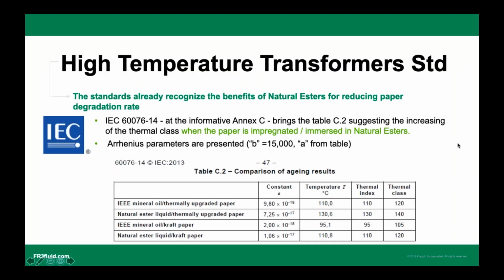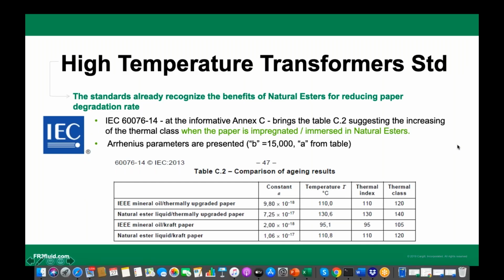So when I say the natural ester K-class fluid becomes the first choice of preference for the customer, especially in the European world and the Western world, it is because now standards are available. There is IEC 60076 part 14, which is a high temperature standard. The standard does allow you to increase your transformer rating to as high as 140 degrees C. That means your transformer becomes almost 1.2 to 1.5 times the rating.